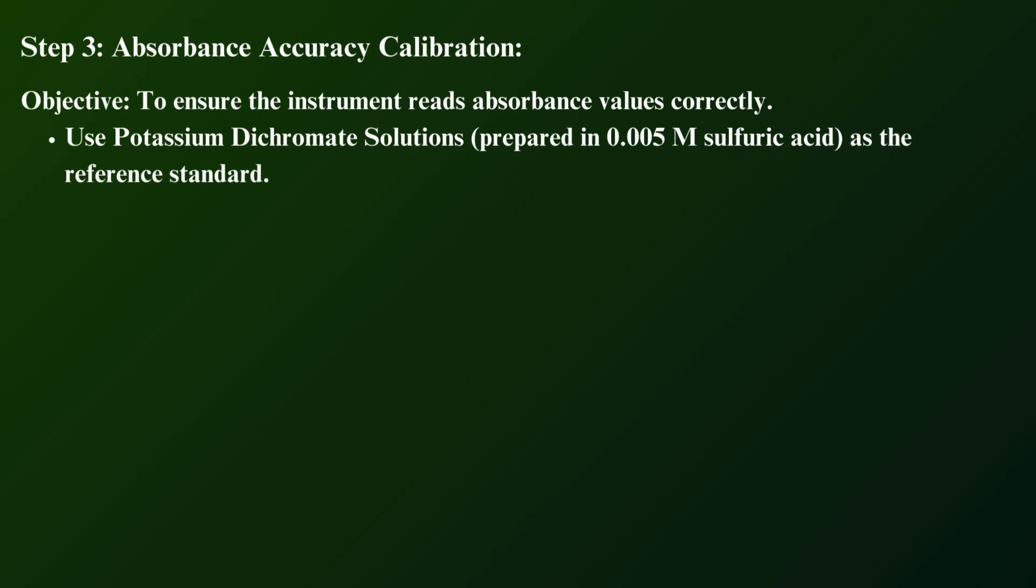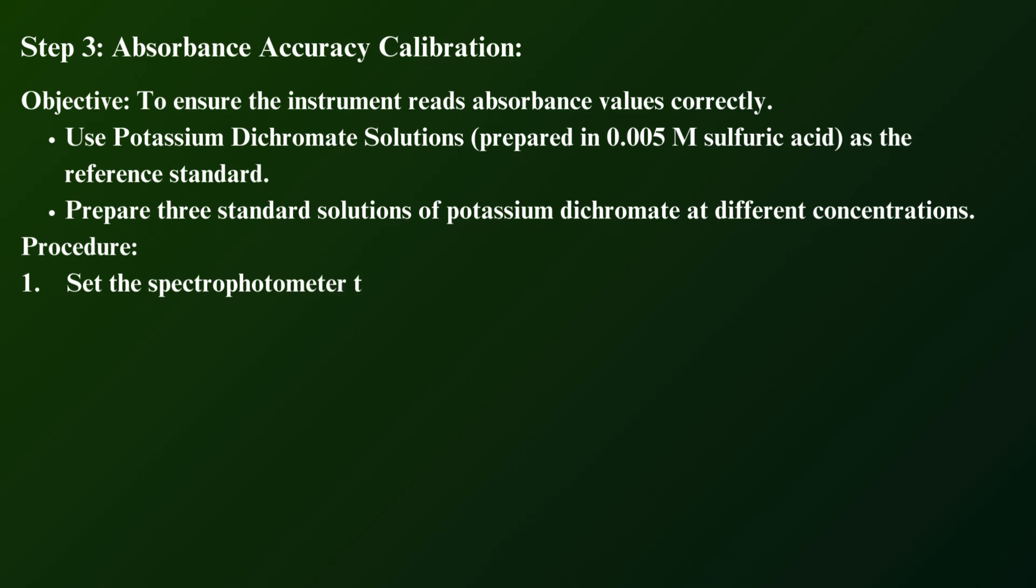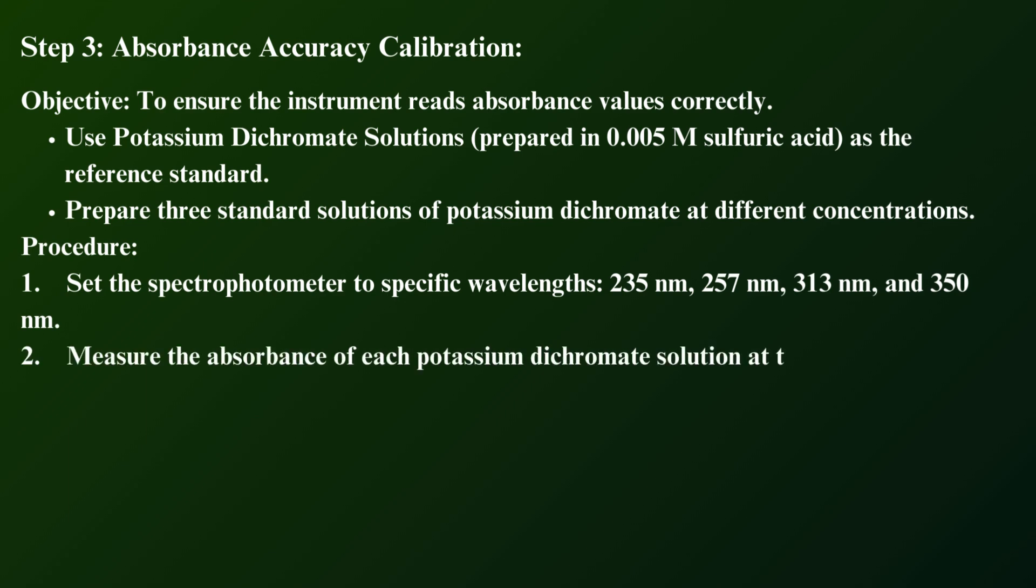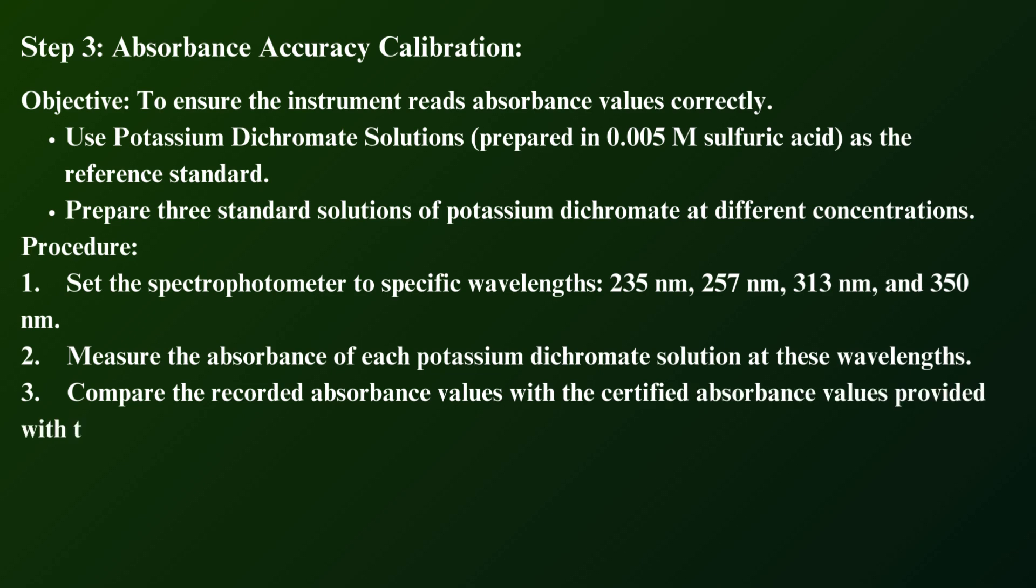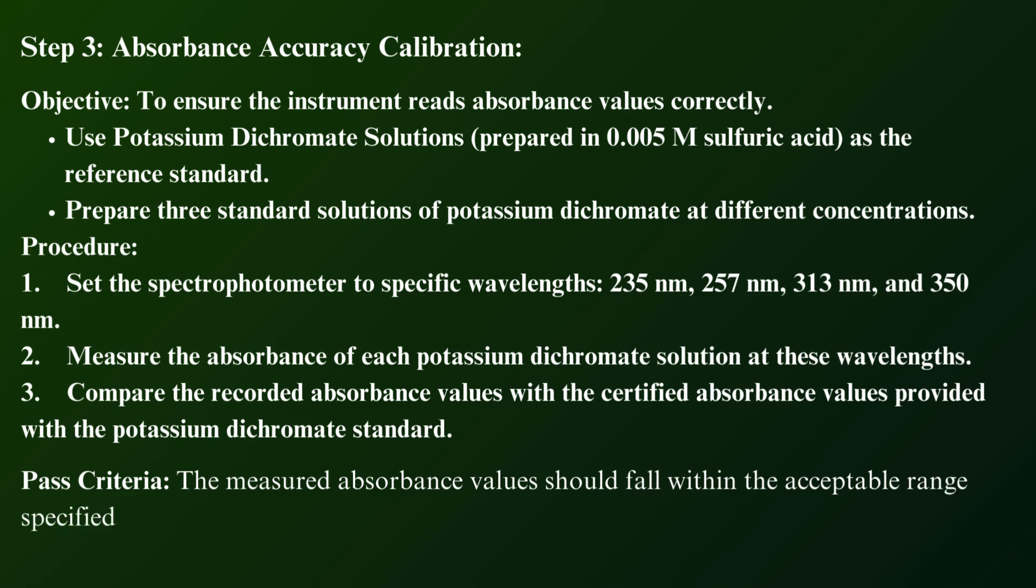Prepare three standard solutions of potassium dichromate at different concentrations. Procedure: Set the spectrophotometer to specific wavelengths: 235 nanometers, 257 nanometers, 313 nanometers, and 350 nanometers. Measure the absorbance of each potassium dichromate solution at these wavelengths. Compare the recorded absorbance values with the certified absorbance values provided with the potassium dichromate standard. Pass criteria: The measured absorbance values should fall within the acceptable range specified in the reference material certificate.